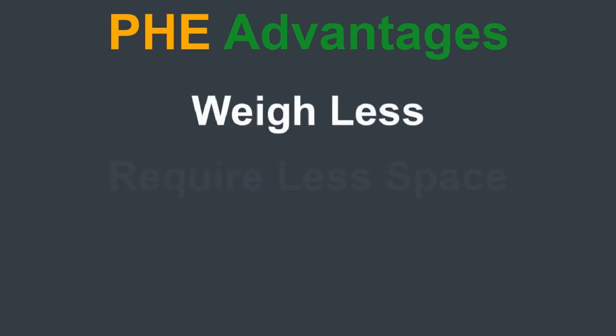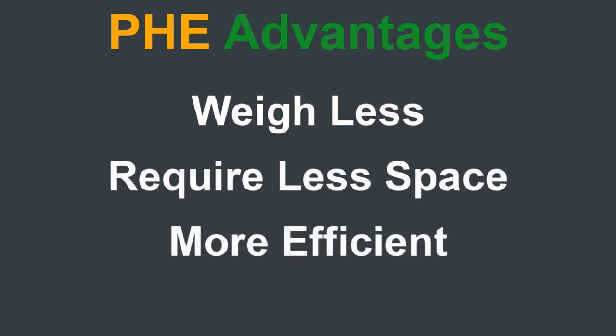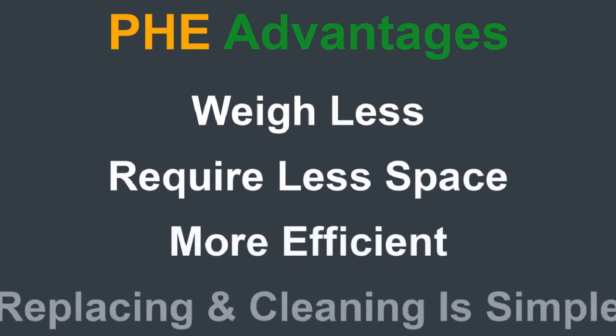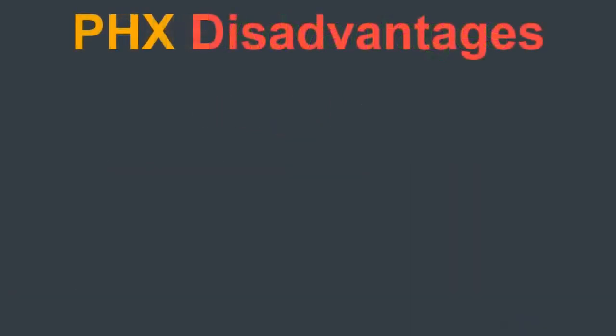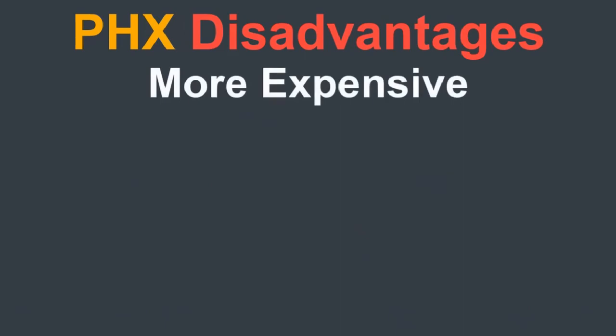There are numerous advantages associated with plate heat exchangers. Plate heat exchangers weigh less, require less space, and are more efficient compared to other heat exchanger designs of the same size. Replacing and cleaning of the plates is a simple task, because the plate stack can be opened easily. And unlike shell and tube heat exchangers, plate heat exchangers do not require additional space for dismantling. But there are also some disadvantages. Plate heat exchangers tend to be more expensive than other heat exchanger designs.